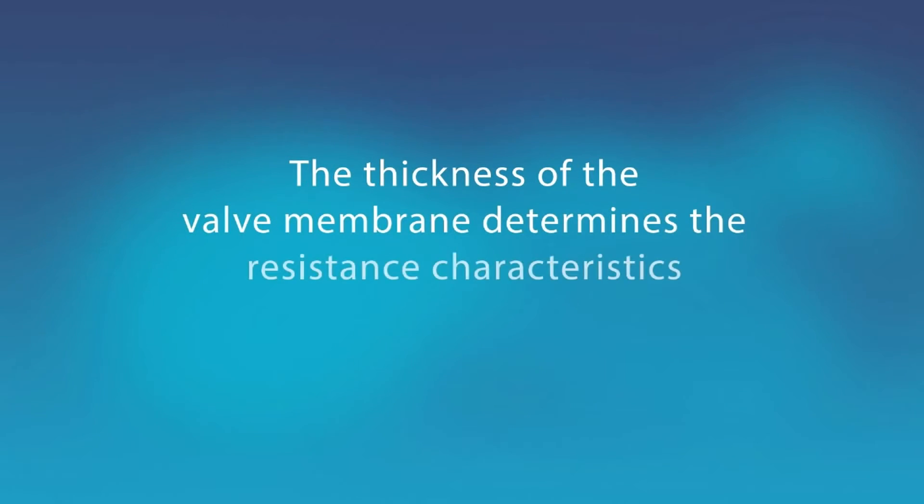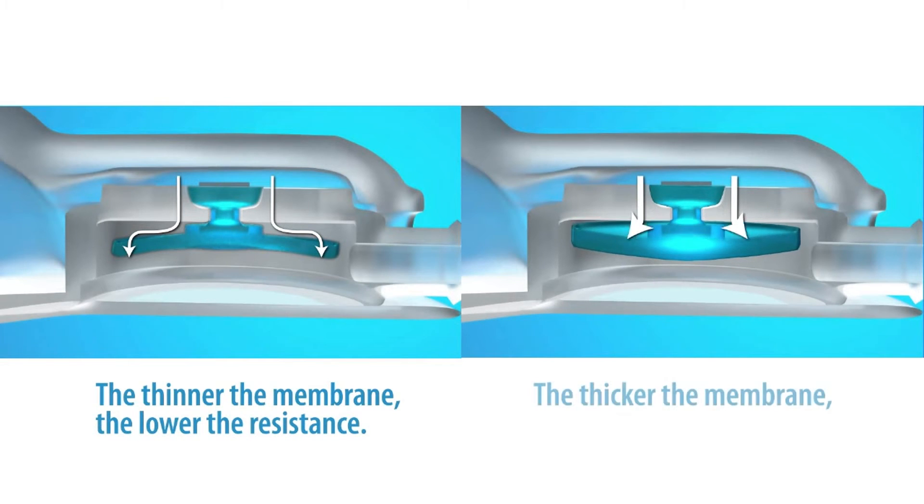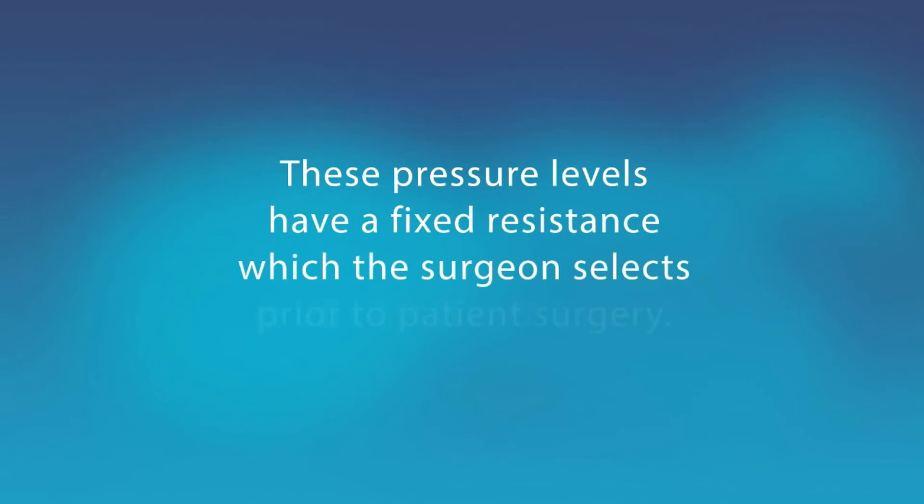The thickness of the valve membrane determines the resistance characteristics of the valve. The thinner the membrane, the lower the valve resistance; the thicker the membrane, the higher the valve resistance. These pressure levels have a fixed resistance which the surgeon selects prior to patient surgery.